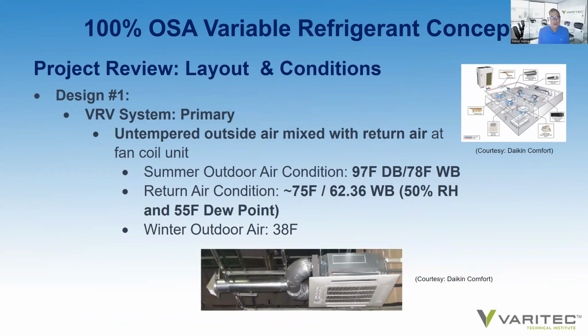So let's look at the three design concepts for the medical office building we have under review to evaluate a 100% outside air VRV solution. Design number one was a VRV system, and it was the primary HVAC system. It utilized untempered outside air mixed with the return air at the fan coil units. We applied a summer outdoor air condition of 97 degrees dry bulb, 78 degrees wet bulb, which is our Arizona monsoon design condition. We looked at a return air condition of 75 degrees at roughly 50% RH to conform to ASHRAE Standard 55 guidelines, and that equals a room or building dew point of 55 degrees. In the winter months, we designed to 38 degrees for this evaluation.